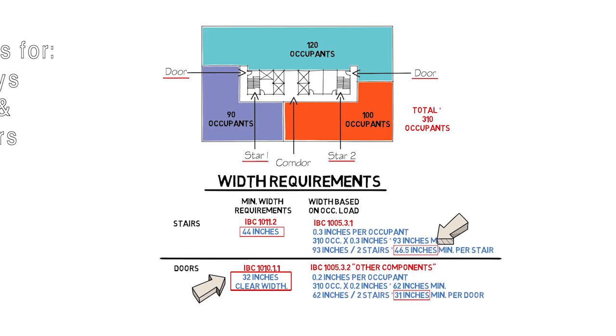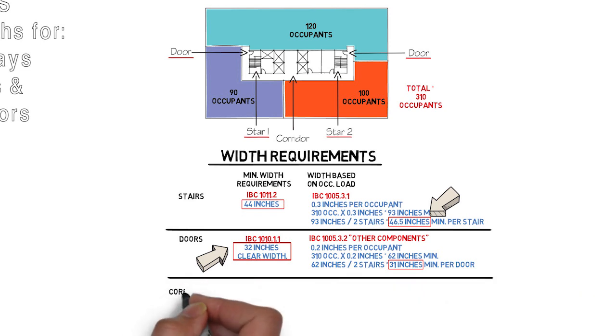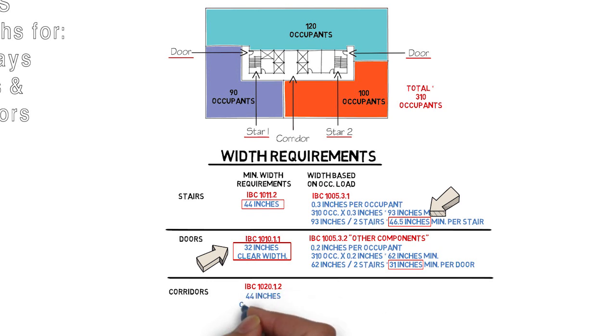Now what about the corridors? Let's start with the minimum widths required by the code. This can be found in IBC section 1020.1.2, which contains a table. You have to determine what type of use your floor has — in our example this floor is used for office. Based on the table, we need a minimum of 44 inches clear for our corridor.